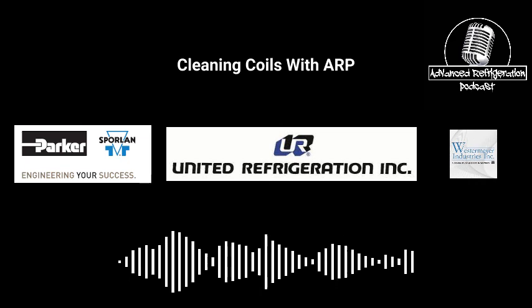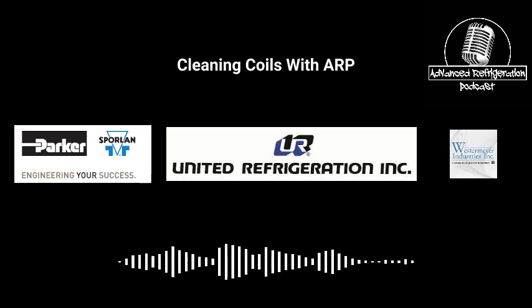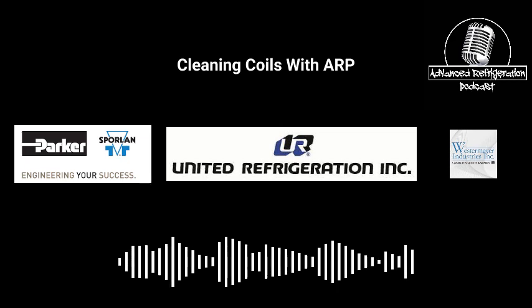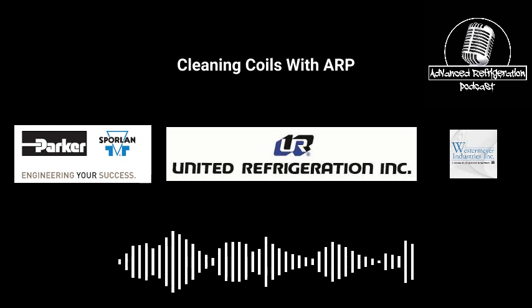That's where TD alarming should be a normal thing now. Especially with all this AI stuff coming in, we should be checking TDs on condensers all the time. You should be looking at it in service calls. If you see the TD on the condenser start going really high, then you know that condenser isn't doing enough work. It's not exchanging enough heat, because your saturation temp's cranked way up and your outside air temp is staying constant. Your condenser is getting less efficient the warmer it gets, and as time goes on. So that's why that alarming should become a normal thing.